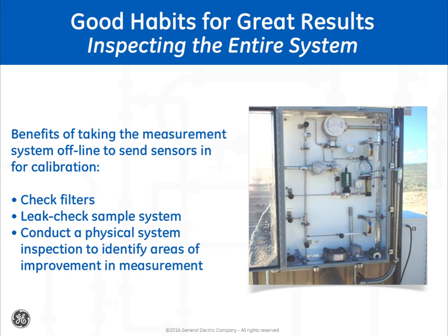Taking the measurement system offline to send sensors in for calibration provides the technician a regular opportunity to check the filters, leak check the system, and allows for a physical inspection that may lead to other areas of improvement in the measurement.